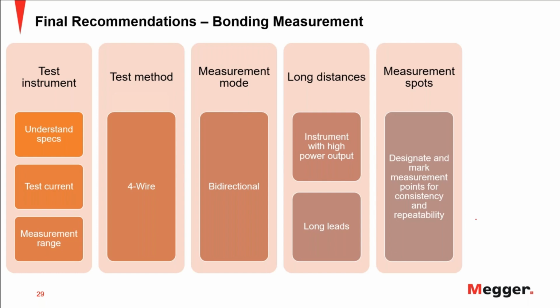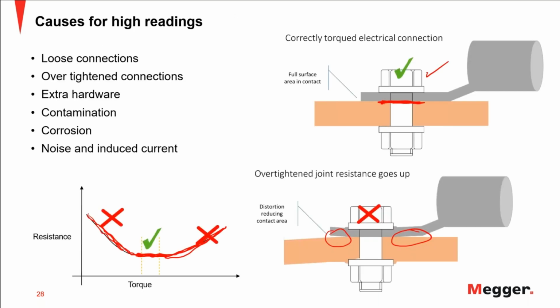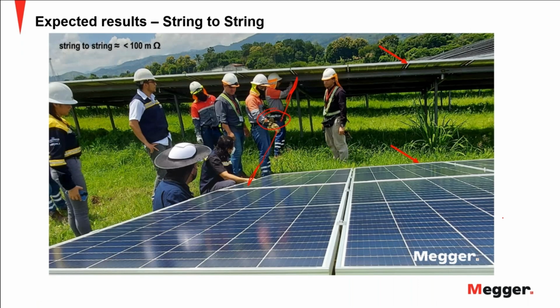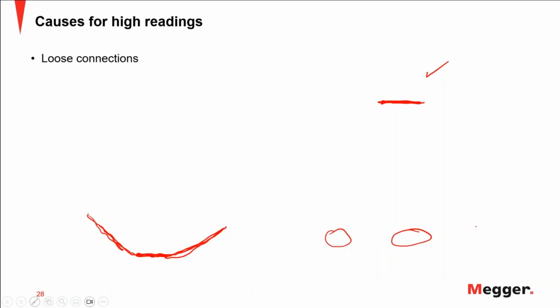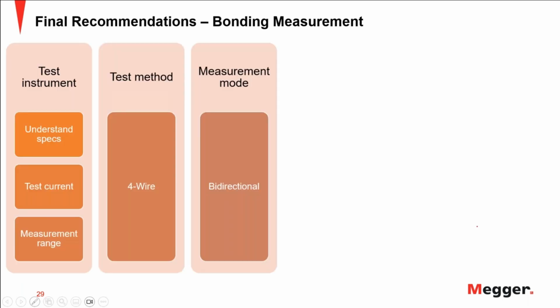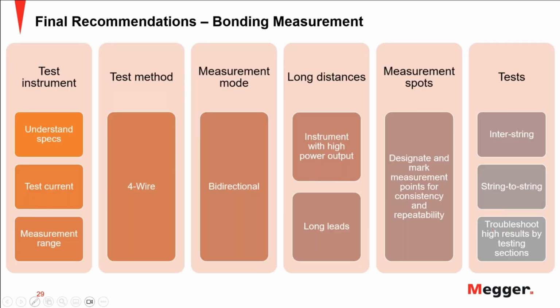And measurement spots, you want to designate and mark the measurement points for consistency and repeatability. So going back to my previous slides, if I'm doing the test, I would like to mark these here for future reference, and this spot also for future reference. That way, every time that I make the measurement, I'm doing a repeatable measurement, and I know that if I get a different result, it's not because I connected to a different spot.